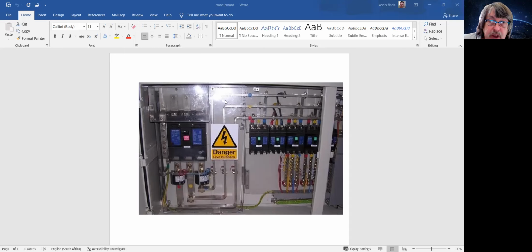So the withstand on here, you can also see that there's no insulation on these. So while they look good and attractive, they could very easily result in something dropping down from the top here, a piece of wire from manufacturing of this type of thing, or a spanner or something falling through the panel, which will also create a short circuit here, an immediate short circuit, I should say. And so without any interface barriers, there's a risk that these would immediately have a short circuit external. Of course, that will damage the product completely, requiring replacement of the circuit breaker that is involved in that.